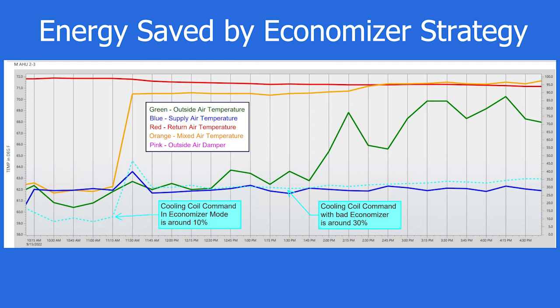And here we have an example showing how much energy can be saved in an economizing strategy. So here we have the economizer operating properly up until about 11:15 a.m. And that is where we see the mixed air temperature rising quite a bit and tracking with the return air temperature instead of with the outside air temperature.